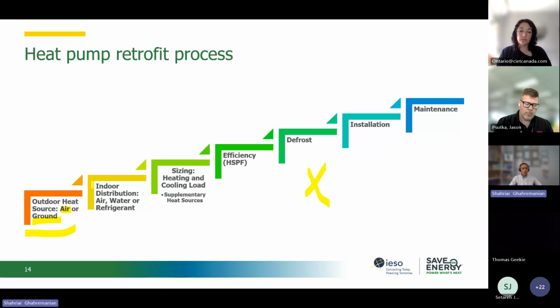The next one is the indoor distribution. So in indoor distribution, we can have air, which is ducts. We can have the chilled water or the hot water piping system, or we can go to the VRF system and actually bring the refrigerants throughout the building. So this is also the indoor distribution that we need for our buildings, actually. After deciding about the outdoor unit and also the distribution system that is best for us inside the building, and I touched on that one, I said that refrigerant is the best one because it's highly efficient, and the size of the pipes and everything becomes very, very small compared to the ducts of air that we need.